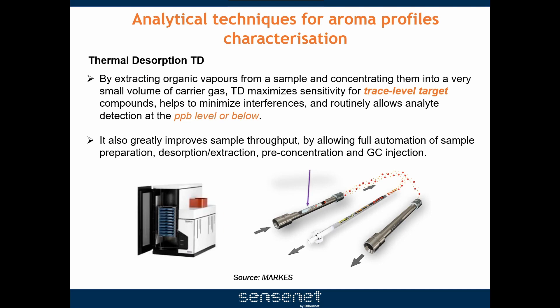We use thermal desorption for odor characterization. By extracting organic vapors from a sample and concentrating them into a very small volume of carrier gas, thermal desorption maximizes sensitivity for trace level target compounds, helps to minimize interferences, and routinely allows analyte detection at the parts-per-billion level or below. It also greatly improves sample throughput by allowing full automation of sample preparation, desorption extraction, pre-concentration and GC injection.